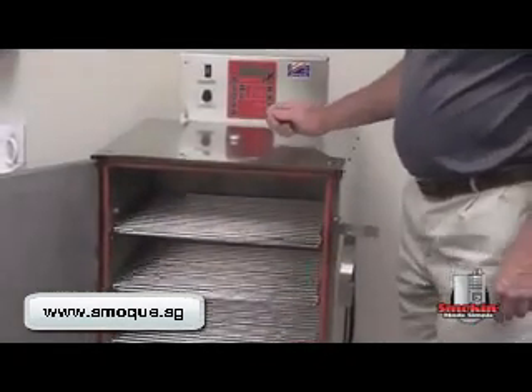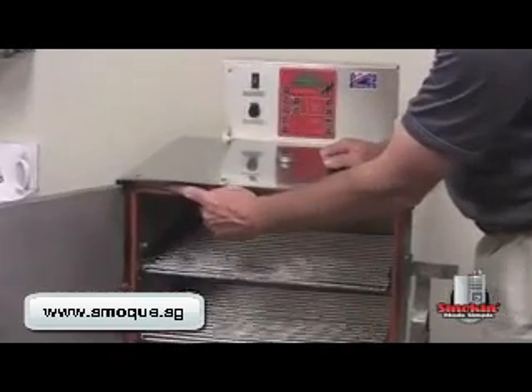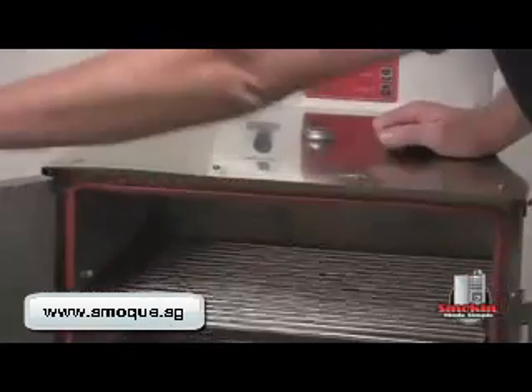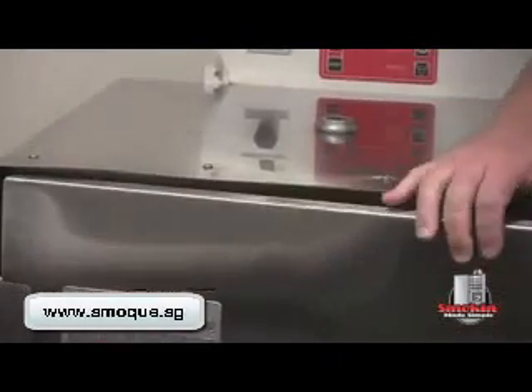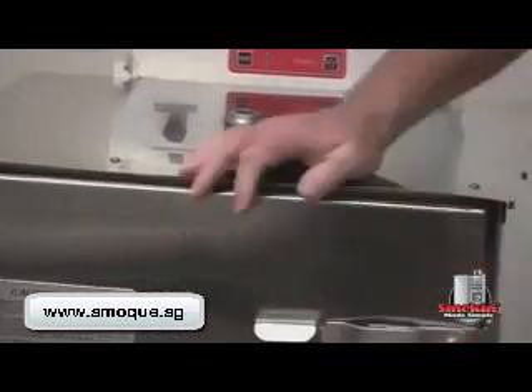In order for the unit to operate, the door closed button has to be in the on position. To do that, we close and latch the door, making sure that we latch both latches securely.